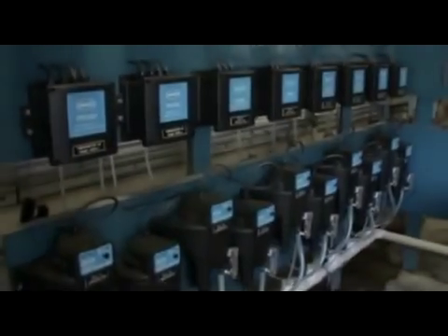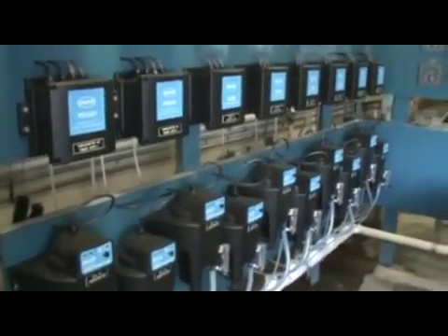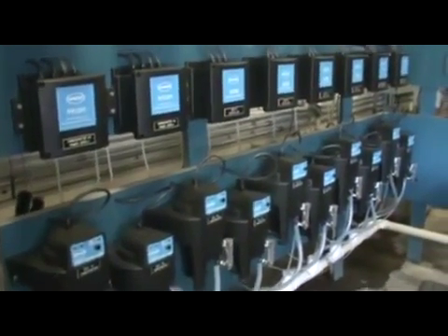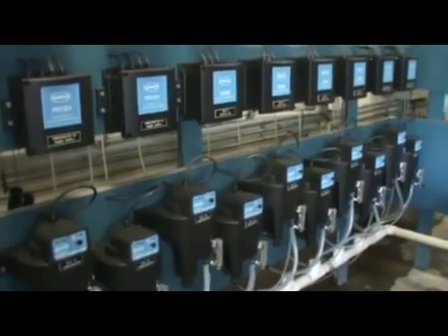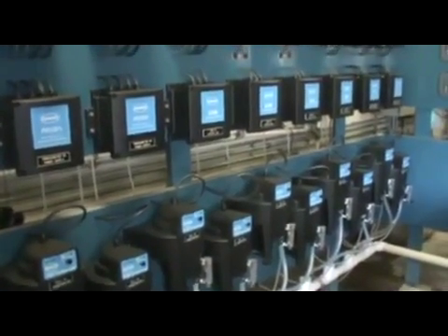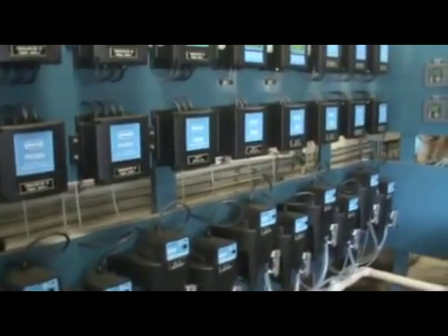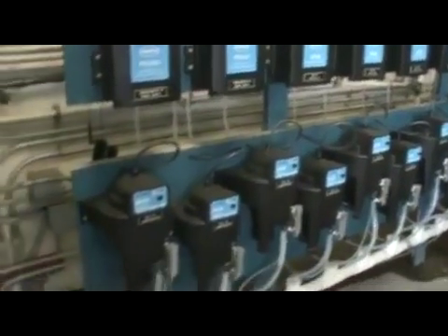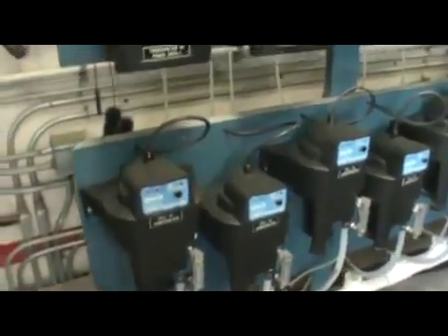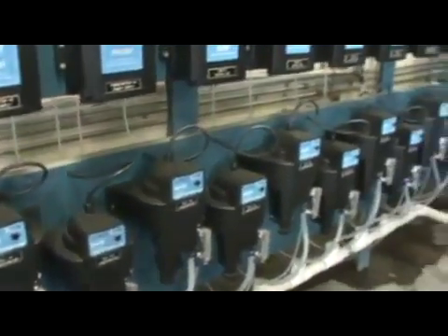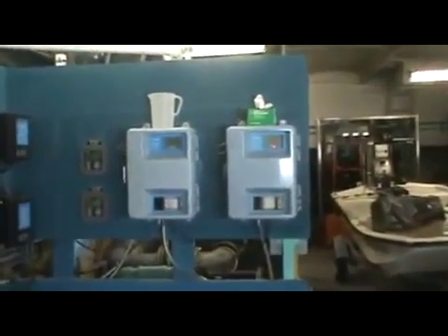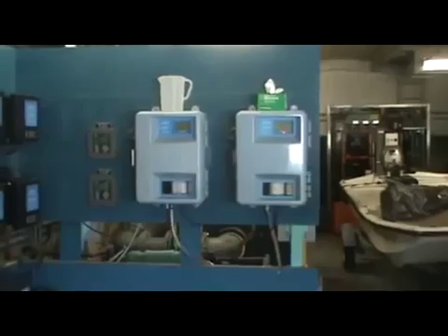Monitoring is an essential part of any water treatment process, and there's monitoring that goes on through the entire process. What we have here is a set of turbidity meters that can monitor the influent water, which they call the raw water, the effluent water or the treated water, and also every single one of those 8 filter cells has its own individual turbidimeter. Basically the water flows through here and it can tell you the turbidity and what's going on in each of those cells. Also there's chlorine monitoring that monitors the pre-chlorine dose and the post-chlorine dose for the chlorine that goes out to the clear well.